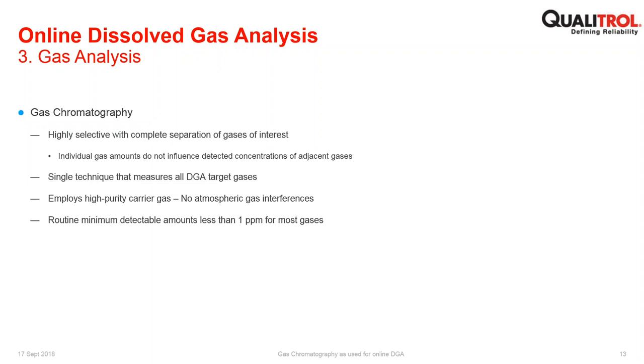Employs high purity carrier gas and no atmospheric gas interference. Again, this is a double-edged sword. You've got to provide the carrier gas in the form of a bottle of helium for the Qualitrol product. But it does avoid the sample of oil ever getting in contact with the atmosphere, and it also avoids the possibility of local contamination. So we're talking about perhaps smog in an urban environment, or car fumes from a nearby car, or leaking sulfur hexafluoride from a circuit breaker nearby. All of these can influence infrared-based systems, because gas chromatography is completely self-contained with its own supply of carrier gas. There is no interference from external atmospheric conditions.